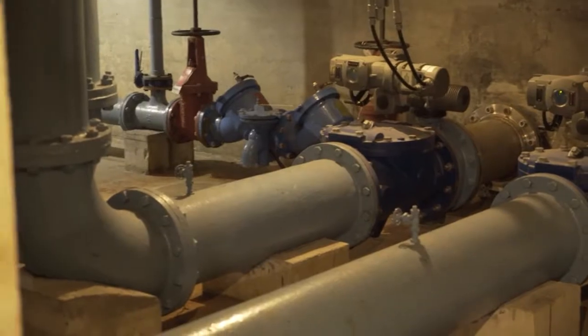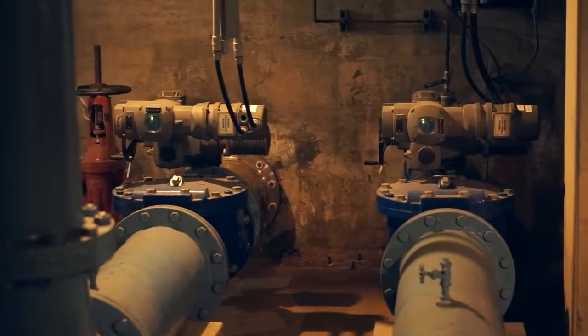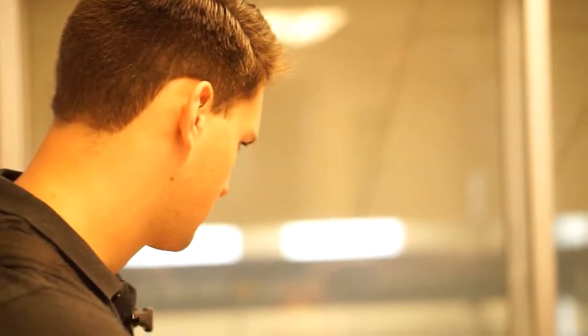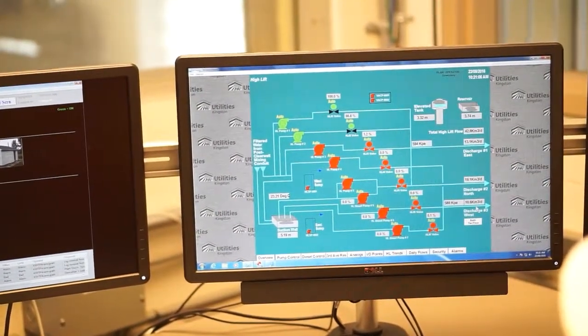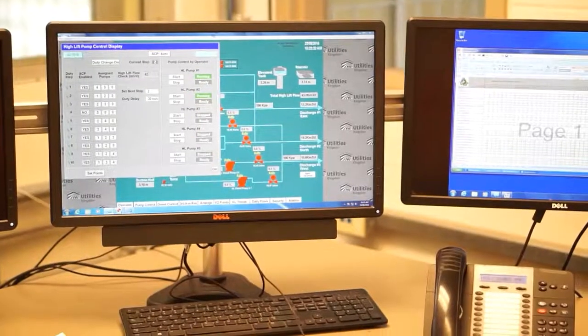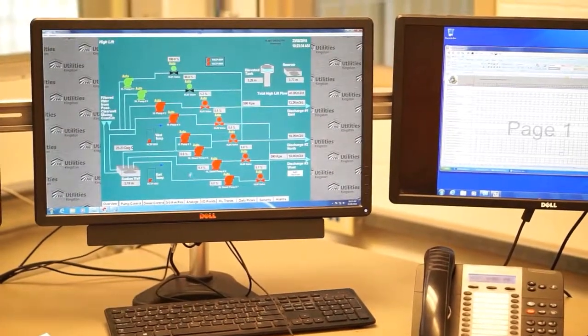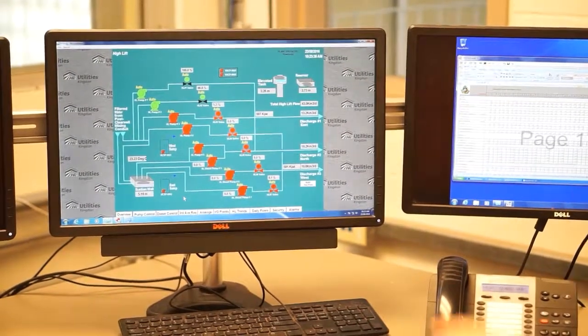The check valves you see here prevent water flowing back into the pump from the distribution system. If these check valves fail to close and water flows back through the pumps from the system, the water flow will spin the pumps backwards like turbines, possibly at uncontrolled and damaging speeds. So, as you can see, pipes and pumps are critical to our daily showers and cooking, things that we take for granted. Some of the best engineering is in systems that work so well, 24/7, 365, that we never even notice.